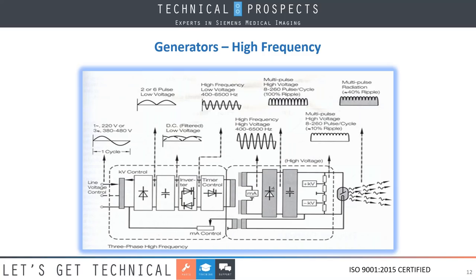The inverter is what gives us the pulsating DC. This pulsating DC is what's applied to our transformer, and then from there we go over to a typical full wave rectified secondary, and this gives us even a smaller ripple because of the fact that we're actually operating at such a high frequency, hence a higher quality X-ray coming out.